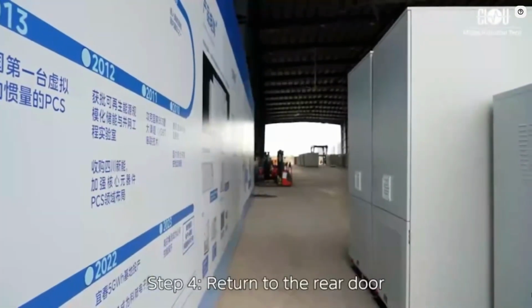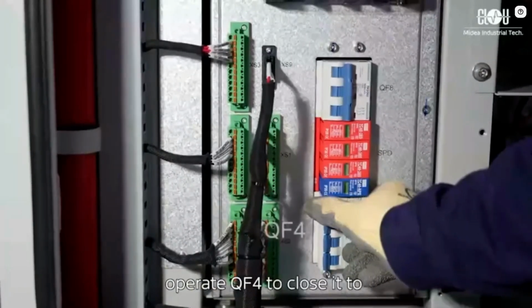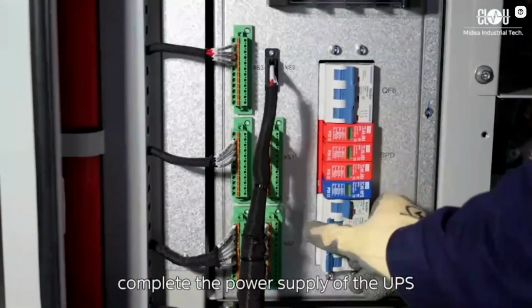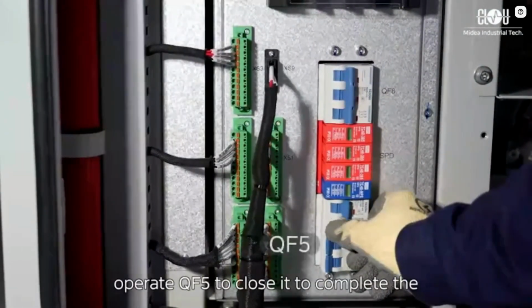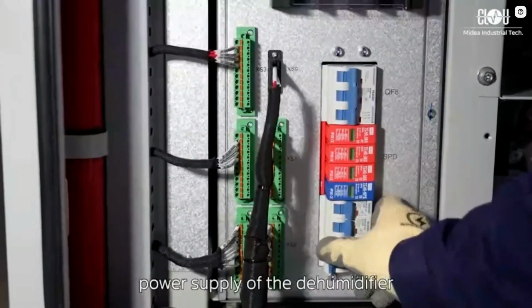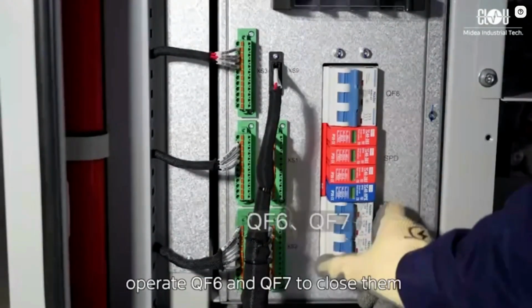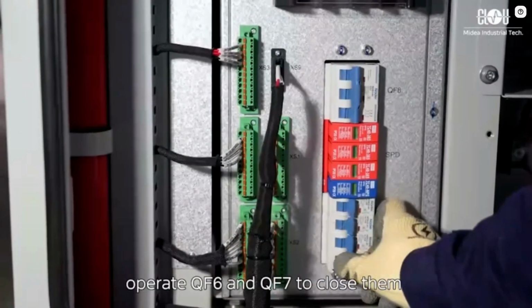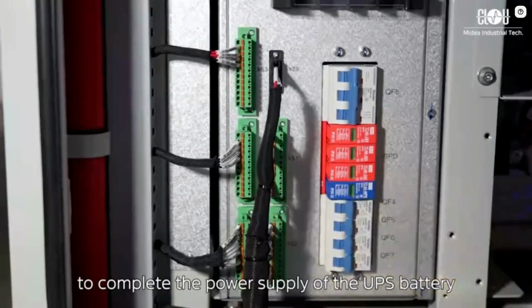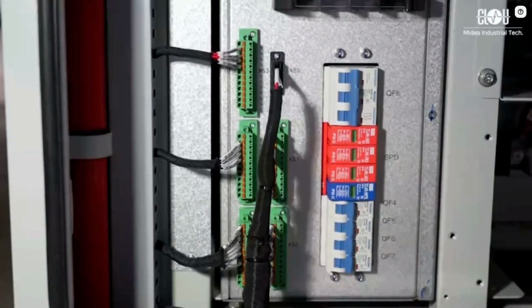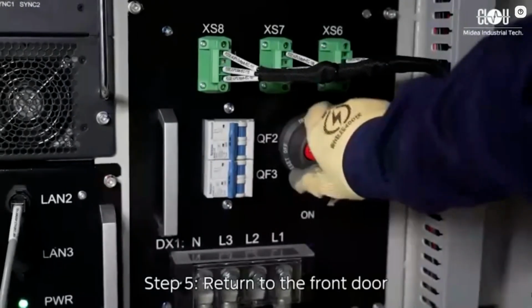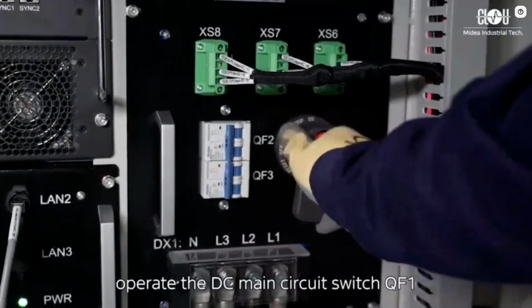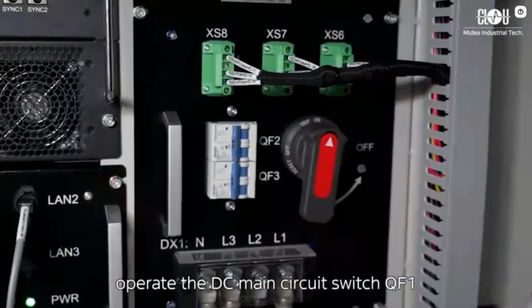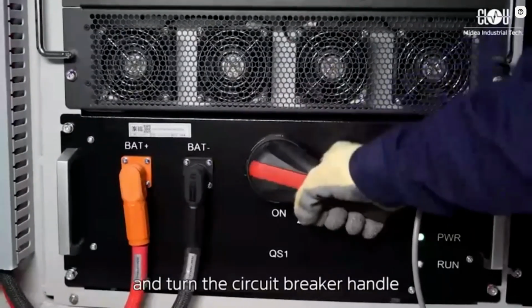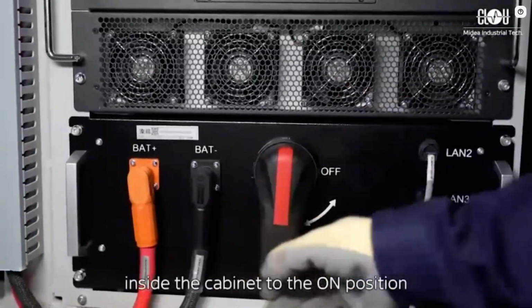Step 4. Return to the rear door. Operate QF4 to close it to complete the power supply of the UPS. Operate QF5 to close it to complete the power supply of the dehumidifier. Operate QF6 and QF7 to close them to complete the power supply of the UPS battery. Step 5. Return to the front door of the energy storage cabinet. Operate the DC main circuit switch QS1 and turn the circuit breaker handle on the control box inside the cabinet to the on position.